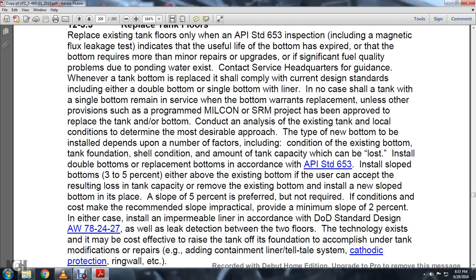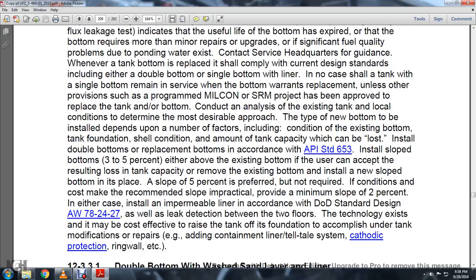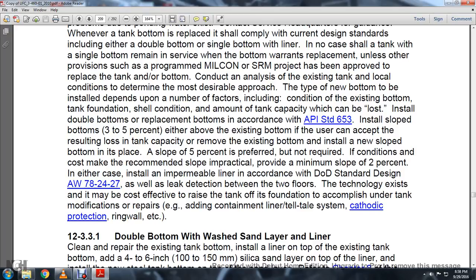Install a sloped bottom above the existing bottom if the user can accept the resulting loss of tank capacity. Alternatively, remove the existing bottom and install a new sloped bottom in its place. A slope of 5% is preferred but not required; when impracticable, provide a minimum slope of 2%. Install an impermeable liner in accordance with Department of Defense Standard Design AW78-2427, as well as leak detection between the two floors. If cost-effective, consider raising the tank and foundation to accomplish modifications including adding containment, inner liner, telltale system, cathodic protection ring wall, etc.